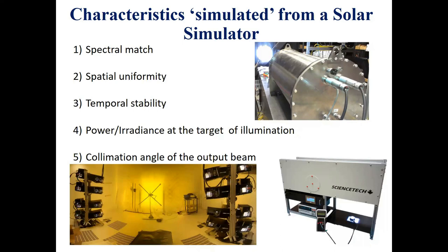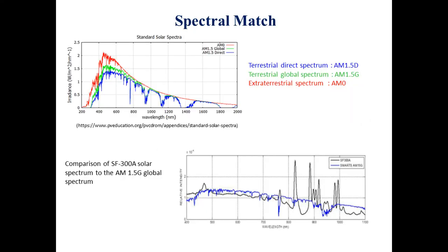The first characteristic we are going to be discussing is the solar spectrum. The figure on the top left shows the wave bands of the spectral distribution for different reference conditions. There's the terrestrial direct spectrum, which is AM1.5D, shown in blue. There's also the terrestrial global spectrum, which is AM1.5G, shown in green. And there's the extraterrestrial spectrum, or what we call the space spectrum, in AM0, shown in red. The figure in the bottom right corner is a comparison of the AM1.5G spectrum to one of our own solar simulators, SF300A — it's a pretty good match. Standards have been developed to regulate how well the spectrum of the solar simulator matches that of the sun.